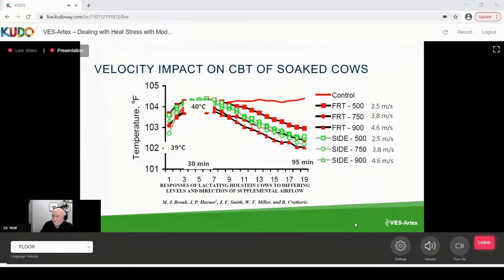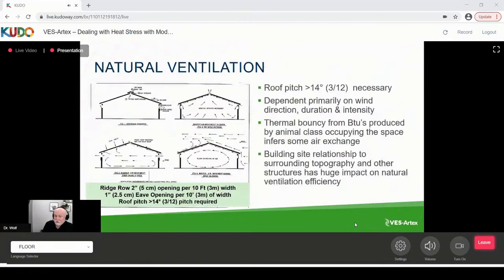So that's getting into how we're putting air at cows that's more advantageous, and it takes higher velocities if it's flowing like in a cross vent situation versus a tunnel barn or a natural vent head-to-head stall situation. So this we're counting on Mother Nature. If the wind blows over the building, we're relying on thermal buoyancy, when there's not that much airflow, to rise up and go out.